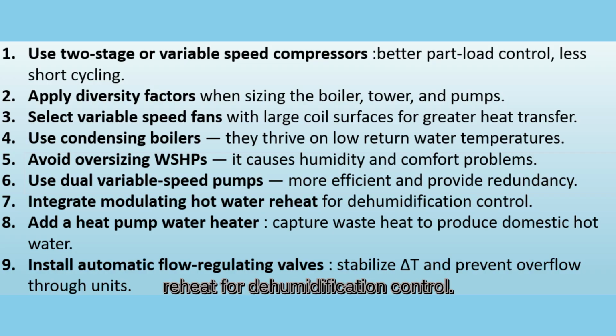Integrate modulating hot water reheat for dehumidification control. Add a heat pump water heater. Capture waste heat to produce domestic hot water. Install automatic flow regulating valves. Stabilize delta T and prevent overflow through units. Water source heat pump systems are the future of efficient, sustainable building design. They combine the decentralization of zone-level control with the energy efficiency of shared hydronic infrastructure. Whether applied in a school, high-rise, or retrofit project, WSHPs deliver comfort, control, and savings, all while supporting decarbonization and net zero energy goals.